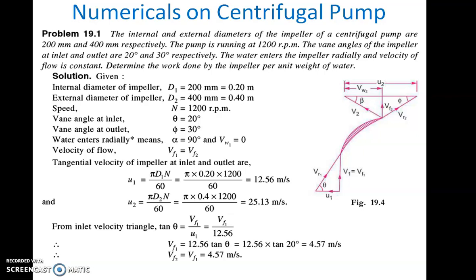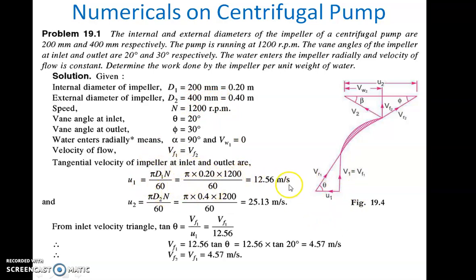We have to find impeller power per unit weight of water. Given data: inlet diameter D1 = 200 mm = 0.20 m, outlet diameter D2 = 400 mm = 0.40 m, RPM = 1200, theta = 20°, phi = 30°, alpha = 90° so Vw1 = 0, and Vf1 = Vf2. U1 can be found as pi D1 n by 60, giving U1 = 12.56 m/s. Similarly U2 = pi D2 n by 60, which is twice U1, giving U2 = 25.13 m/s.